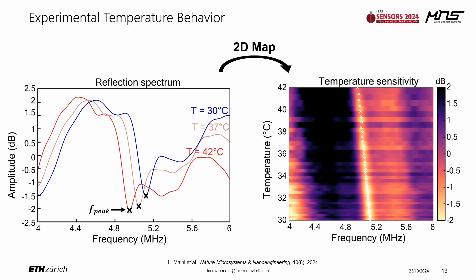When we compute resolution and sensitivity, we do it with a normalization with respect to these values T0 and F0, which are the closest temperature recorded to 37 degrees Celsius and the frequency peak of the FFT detected at 37 degrees Celsius. And the sensitivity is computed as a ratio between this quantity delta F, which is the normalization of the frequency peaks, and delta T, which is the difference with respect to T0. The resolution is computed as the standard deviation of the residuals divided by the sensitivity, where the residuals are the difference between our experimental data and the linear interpolation of our data.